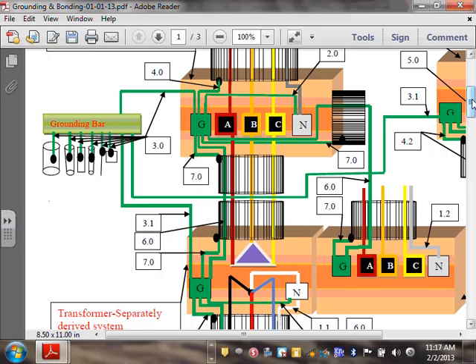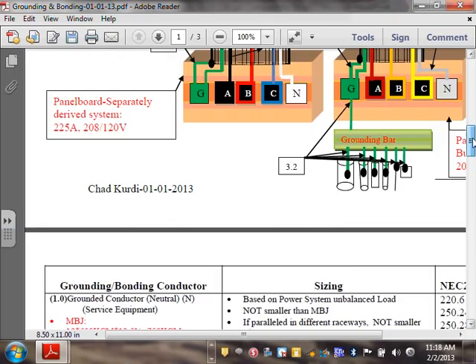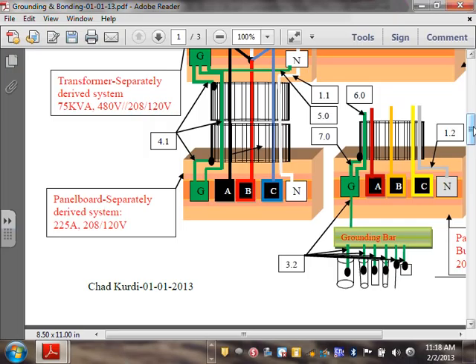Yes, sir. Detached building. You're absolutely right, a very good point. By the same token, Chad, it could apply to your separately derived building right here. What happens if I lost the neutral coming to the building here in the separately derived system? You're going to burn equipment. Yeah, but I see your point though.